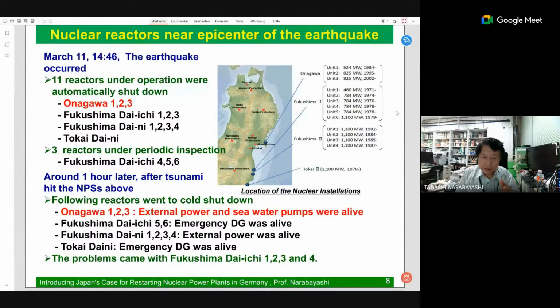At Fukushima Daiichi, units 5 and 6 had emergency diesel generators that survived. At Fukushima Daini, units 1, 2, 3, 4 retained external power. At Tokai Daini, the emergency diesel generator survived. This is very important: even in a strong earthquake and tsunami, having AC power supplied from the emergency diesel generator is crucial to protect against core damage and core meltdown. The problem arose at Fukushima Daiichi units 1, 2, 3, and 4. Next, please.